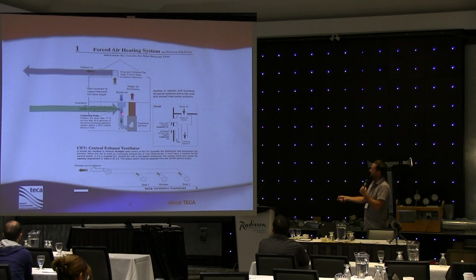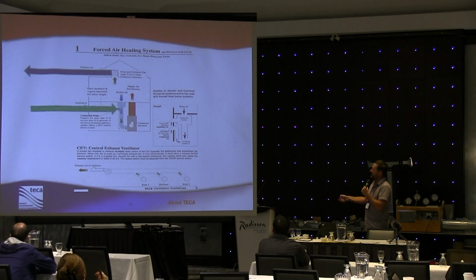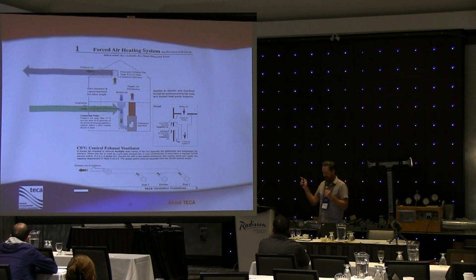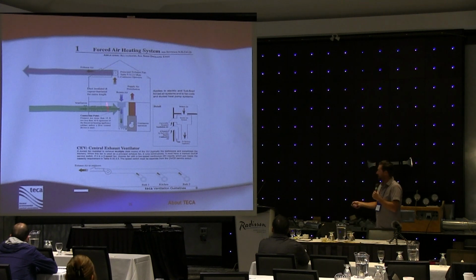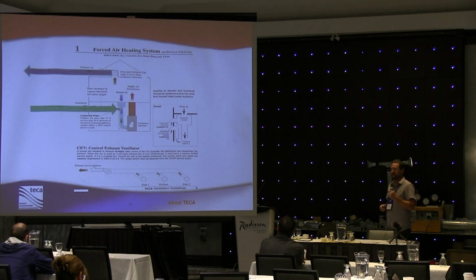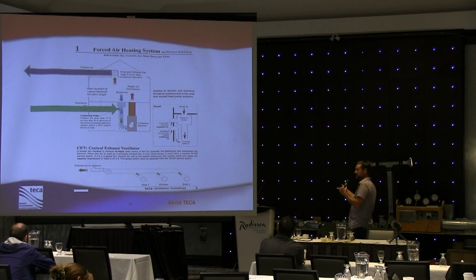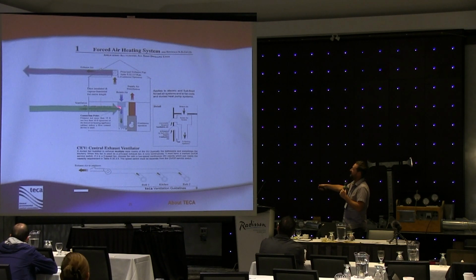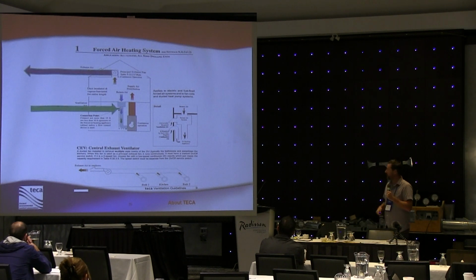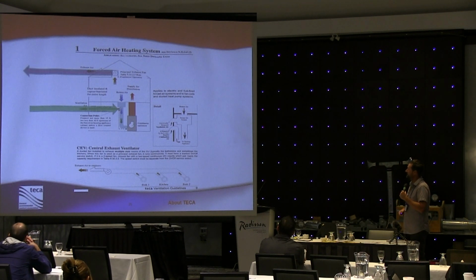What happens is this forced air furnace is set up so that the furnace blower motor, this is the fan that's moving the conditioned air throughout the building, is going to be running on its lowest speed setting possible, and it's also going to run continuously. So what happens is it draws its fresh air in because it creates a little bit of a low pressure area inside this ductwork. This fan is basically creating low pressure by sucking air through the return air ductwork. And when it does that, that lower pressure gives us the ability to tie a duct from outside into it and draw that fresh air directly into the return air plenum of the furnace. That indeed brings in enough fresh air for us to satisfy the ventilation needs for the home.